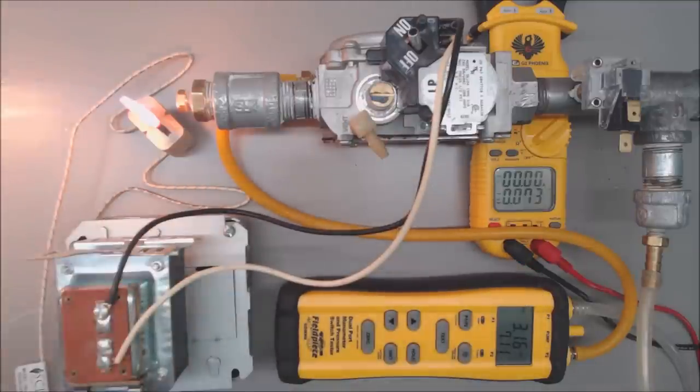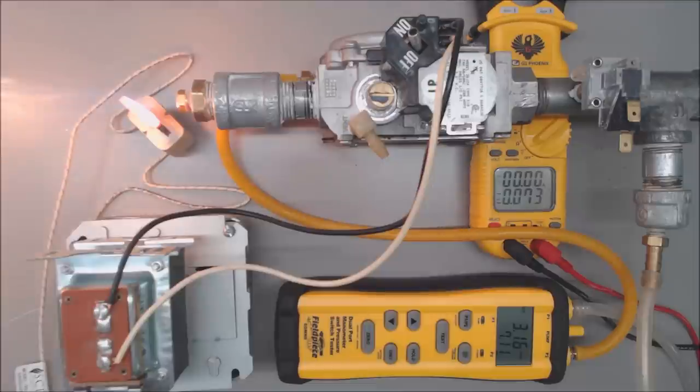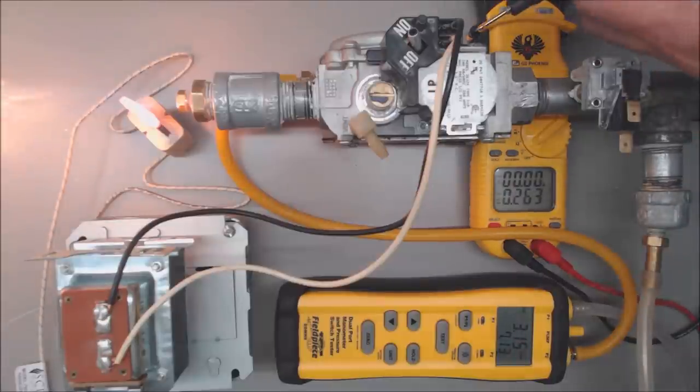So that could make a rough ignition. It may have just been rough igniting for a long period of time and then now it just won't ignite at all, but that's how you determine what the problem is. We also want to read our 24 volts.